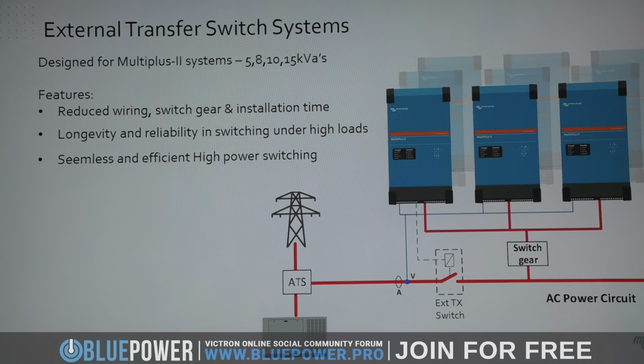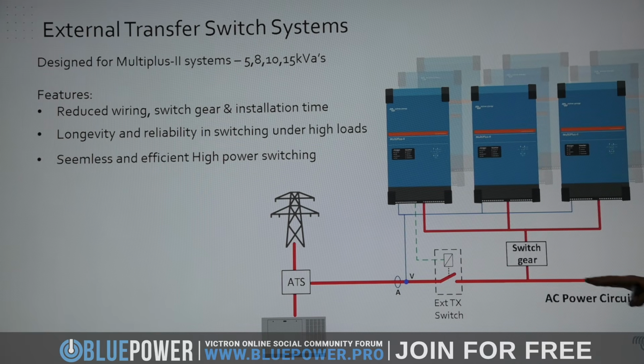If you do a data center or an N+1 system, they all have a common AC bus, and everything connects to that bus to supply the load. So you have generators and grids and multiple generators. That's how most of the guys are doing it. It's not voodoo or the black arts that a lot of people use. The whole idea is to reduce the wiring and the switch gear, because the Multiplus 2s already come at quite a nice price advantage. So now you can go this way and offer something a little bit extra, to improve longevity and seamless high power switching.